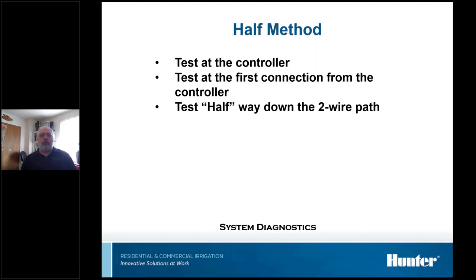The one thing I advise everybody when you do this, you don't have to disconnect both wires. You don't have to disconnect both the red and the blue, but you got to disconnect one of them and stay consistent. I disconnect blue wires. I have no reason why it's the blue wire I use other than I disconnect blue wires. But you do need to stay steady. If you disconnect red on one and blue on the other, and that extra wire in both cases touching ground, you can get a current path through them. But you don't have to disconnect both, just one of them. That'll tell you. So you disconnect, you go back to the controller, and you see what happens.